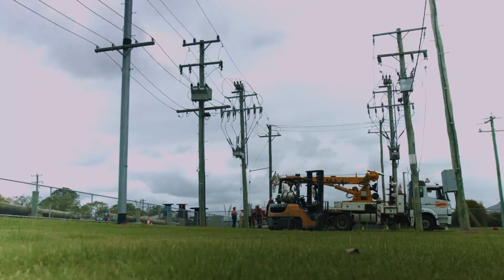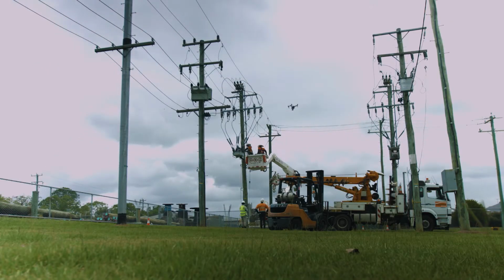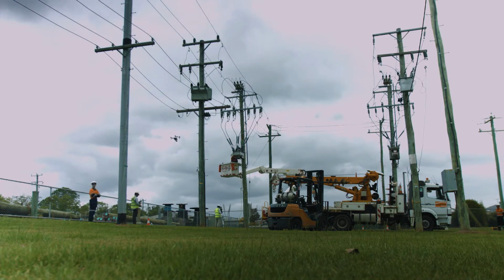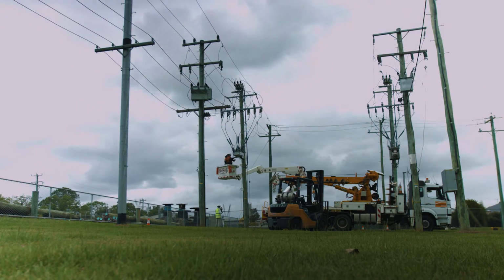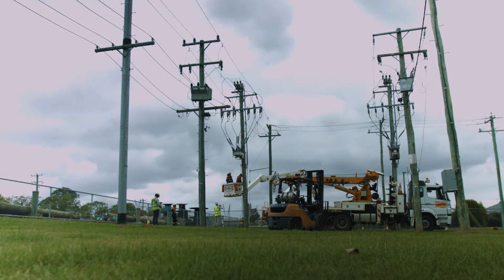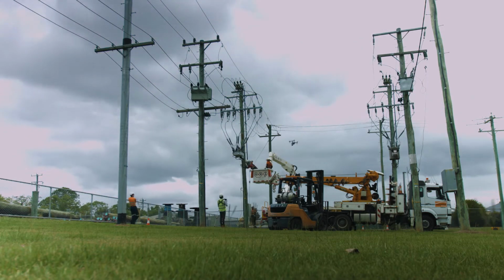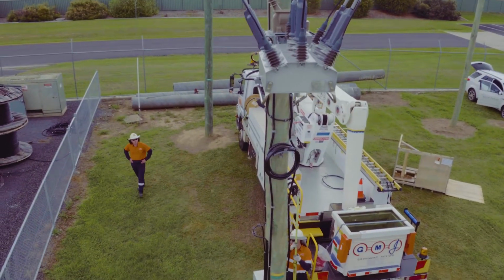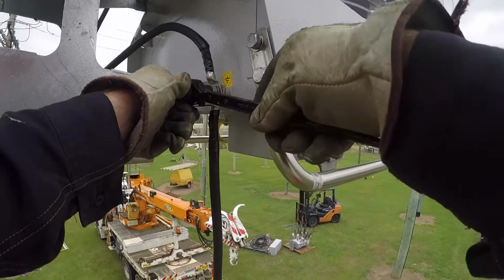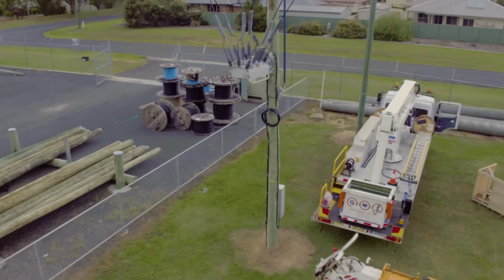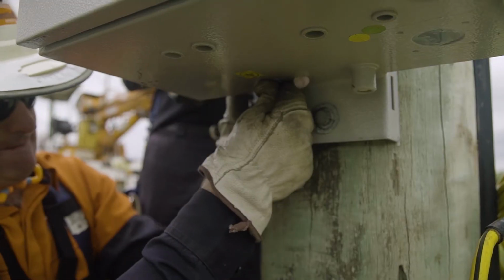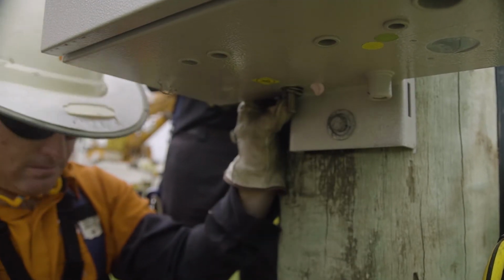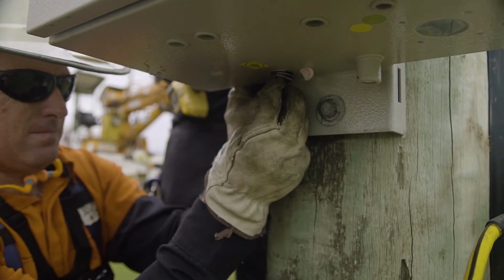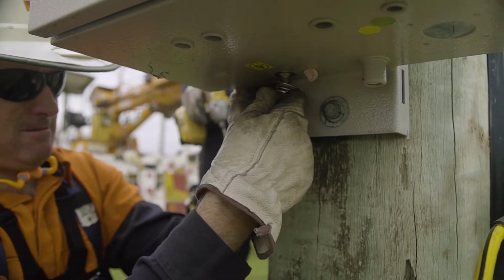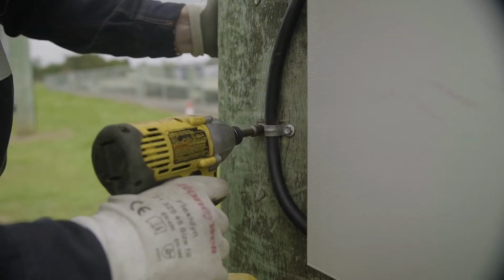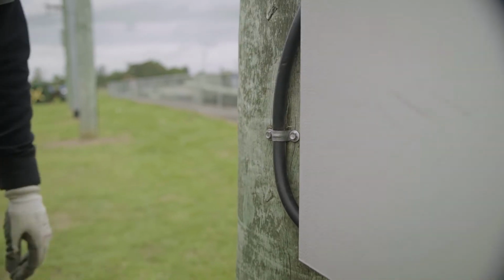Other materials such as aluminium or steel used for earthing are not acceptable for this equipment. Resistance to earth must be maintained within your local regulations for the installation of this type of equipment. The earthing conductor must be unbroken from the recloser to the earthing point at the base of the pole. Connect the control cubicle to the main earth using a line tap or a parallel groove clamp. At least 35mm square copper conductor with the shortest possible distance should be used.